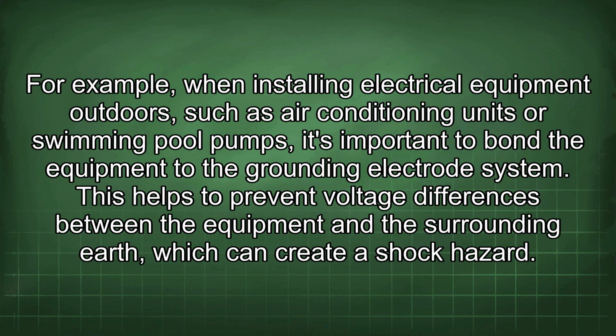For example, when installing electrical equipment outdoors, such as air conditioning units or swimming pool pumps, it's important to bond the equipment to the grounding electrode system. This helps to prevent voltage differences between the equipment and the surrounding earth, which can create a shock hazard.